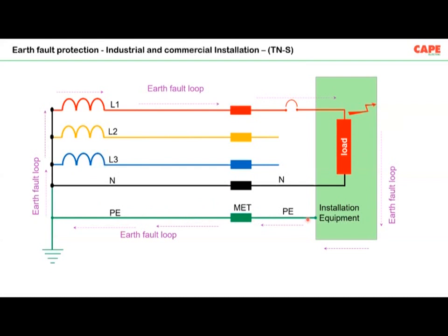Installation or equipment earthing means the impedance of the conductor must be very small. That means no loose contact, sizes must be higher, and so on. Another requirement is the protective conductor must run very close to the phase conductor, or phase and neutral conductor. The idea is whenever there is a fault current flow through the protective conductor, the loop is reduced to a very low level. As a result, the electromagnetic effects, or the mechanical force effects, are reduced. So basically, in industrial and commercial installations, we are supposed to have a five-wire system.